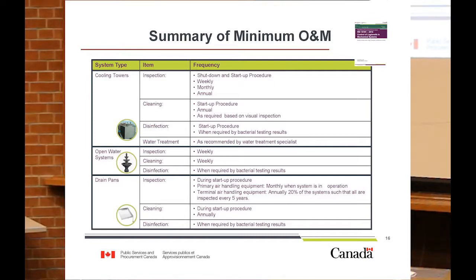Disinfection of the towers is required at system startup, and also when required by bacterial testing results, which we'll talk about in a minute. Open water systems are similar, but they have less mandatory frequency associated with them. For drain pans, we're focusing more on making sure that drain pans are draining properly and that we don't have stagnant water in them. We also look at a difference between primary air handling equipment, which would be like main HVAC units serving multiple areas in a building, versus a terminal HVAC unit, which could be just locally within a space, a small fan coil unit.